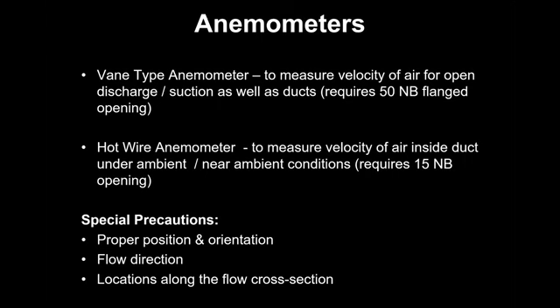Exactly like a windmill. It is giving you power. Here it will just give velocity because this is a small instrument. Then the second one is a hot wire anemometer. This is a specialized instrument normally for clean air at either air conditioning or normal temperature. Basic range is maybe 5 degrees to 50 degrees or 40 degrees. It will not work beyond that.